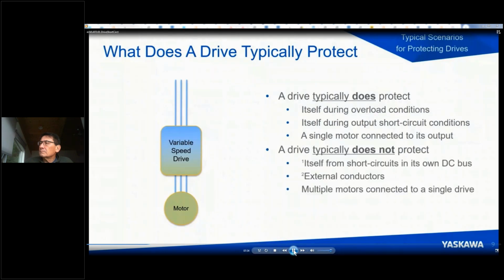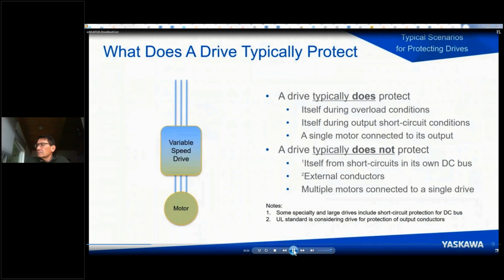But what does the drive typically not protect? It typically does not protect itself from short circuits in its own DC bus. It also typically does not protect external conductors or multiple motors connected to a single drive. There are a few exceptions to that, because there are some specialty and large drives that include short circuit protection for DC bus, in other words, built-in fuses. And an example of this would be the Yaskawa U1000 matrix product.